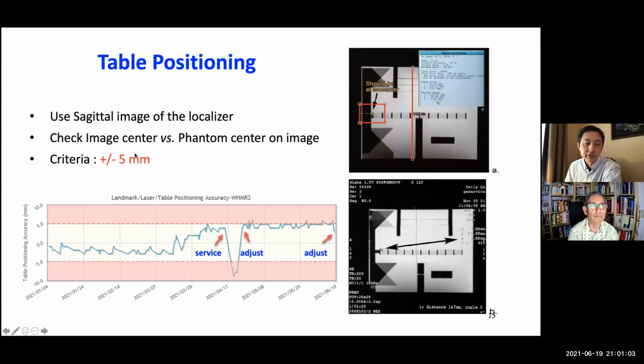ACR has very generous criteria, which is ±5 millimeters. Okay, that's because for diagnostic radiology, the laser landmark is not very critical. For therapy, it's a different story, but for diagnostic imaging, typically, if you are off by 5 millimeters, it's still within the field homogeneity area. So the image quality will not be affected.